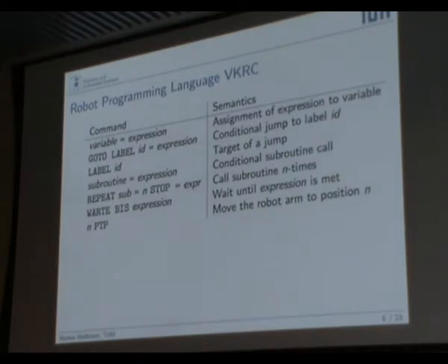The most important commands probably are the movement commands that say, okay, from the current position we're moving to the next position. So the path that the robot actually moves is most of the time a fixed one. If it gets a signal like start, it will move along a concrete path, then activate its welding gun, move along a line, do its welding, deactivate the welding gun, and move somewhere away. And of course you have some control flow in there, like for example, when the robot detects that the welding gun is not working so well anymore, it will go to a repair station and get the welding gun repaired.